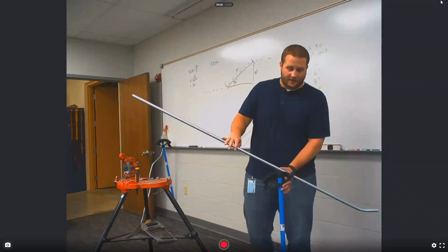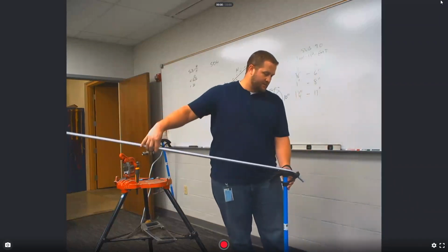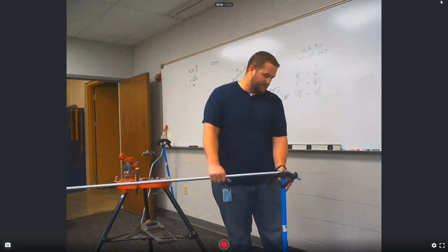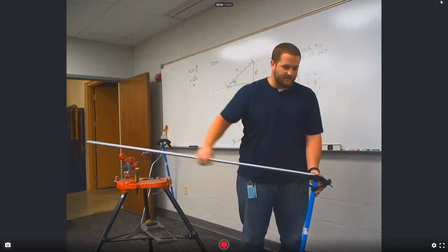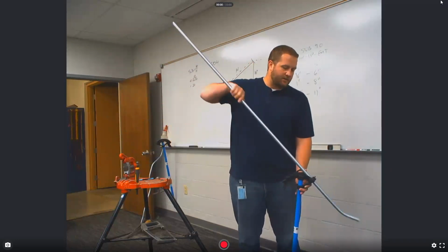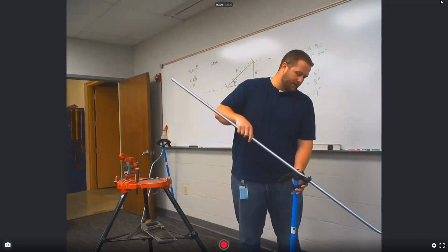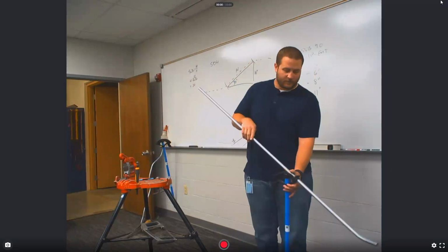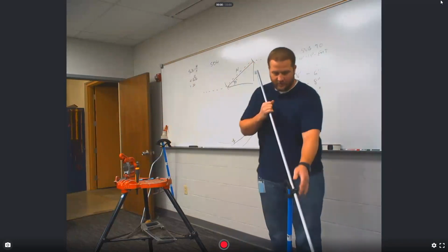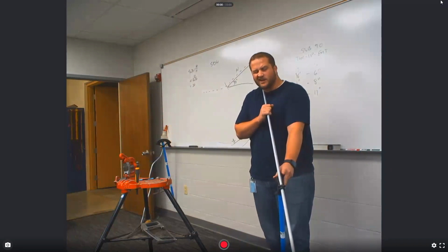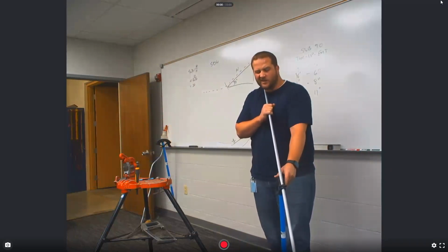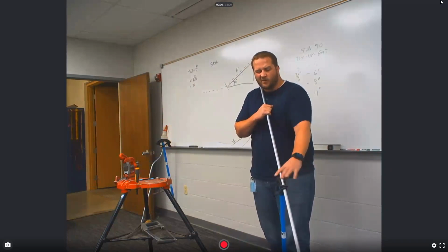I'll show you that again. Okay, I just made my first bend down to 30 degrees, lift the end of the pipe up, push it through, and spin it 180 degrees in one fluid motion. Then I look and eyeball to make sure that it's lined up with the handle of the bender so I don't put a dog in it.